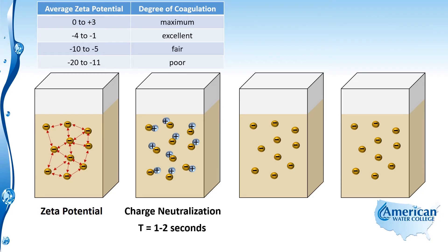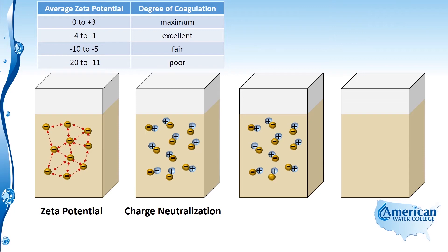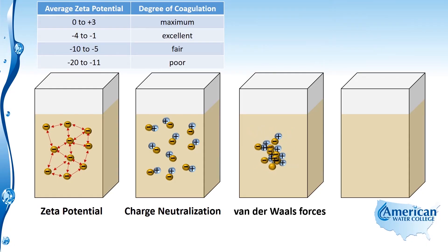Now that we've neutralized the charges, van der Waals forces come into effect. Van der Waals forces is the force between all objects that tries to pull them together. It's not until van der Waals forces overcomes the zeta potential that these colloids can come together and form a floc. By neutralizing the zeta potential, van der Waals forces can then go into effect and our micro floc can become macro floc.